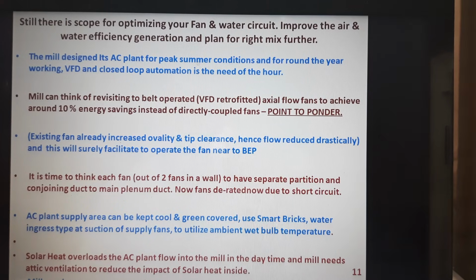The solar heat loads are there throughout the mill, so definitely attic ventilation plays a major role, especially in all the textile mills. You can definitely go for attic ventilation, provided all the ducts are insulated above the ceiling and above the attic condition, and you can see to it that the solar heat, almost 50% of which is getting ingress into the mill side, can be at least partially removed. The mill needs a green cover around so that it serves as a canopy when viewed from a drone as such.